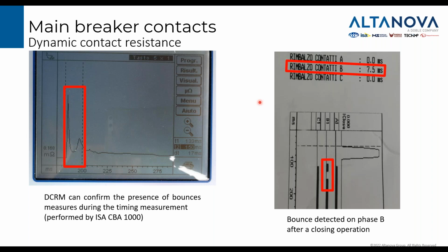Most probably it is a problem in the mechanism. For example, the main contact closes, but there is a problem in the mechanism, so there is a bounce, and it's not touching very well here, and then it returns to the close position. So it is important to combine the two measurements, because sometimes the two measurements confirm that this is a real problem. So you can avoid doubts. Maybe you can doubt that this is a good measurement, but if two different measurements with two totally different approaches give the same information, you can safely say that the measurement is reliable.